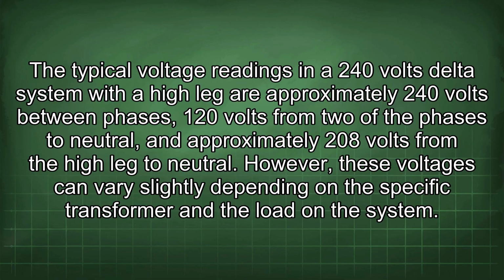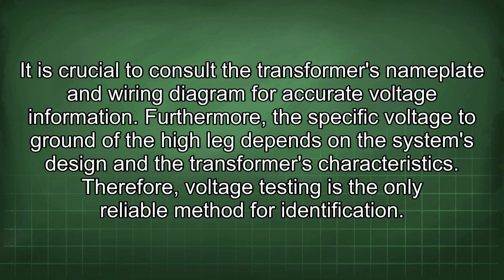However, these voltages can vary slightly depending on the specific transformer and the load on the system. It is crucial to consult the transformer's nameplate and wiring diagram for accurate voltage information. Furthermore, the specific voltage to ground of the high leg depends on the system's design and the transformer's characteristics. Therefore, voltage testing is the only reliable method for identification.